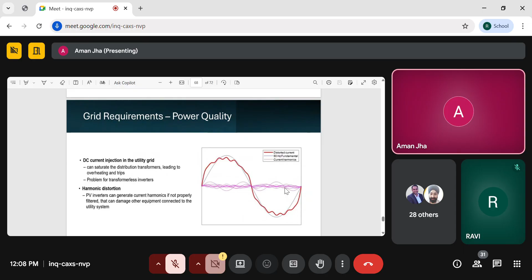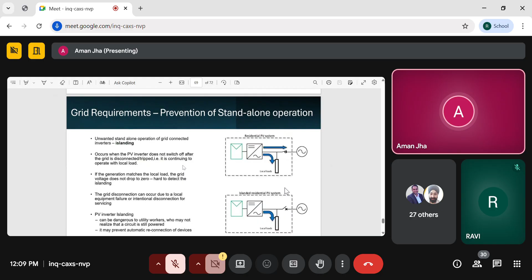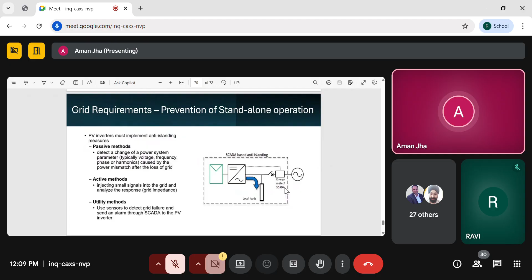This is the discussion of the islanding effect. Unwanted standalone operation of grid-connected inverters occurs when the PV inverter does not switch off after the grid is disconnected. That is very important. It continues to operate with the local load. If the generation matches the local load, the grid voltage does not drop to zero, so it is hard to detect. The grid disconnection can occur due to local equipment failure or intentional disconnection for servicing. So prevention of standalone operation is very important. And how do they do it? They do it by passive methods, active methods, or utility methods.